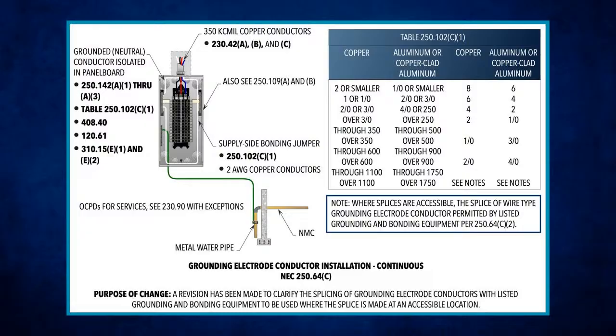And it says, if the grounding electrode conductor or bonding jumper connected to a ground ring as described by 250.52A4 does not extend onto other types of electrodes that require a larger size of conductor, the grounding electrode conductor should not be required to be larger than the conductor used for the ground ring.